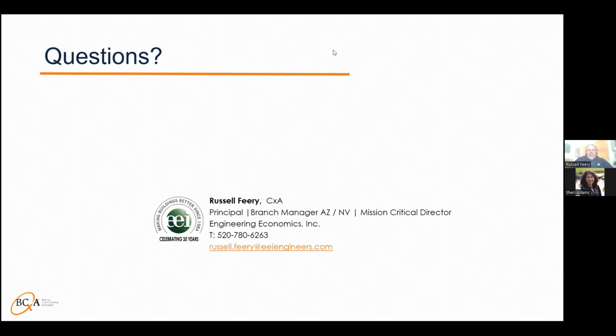Sherry, are you monitoring the Q&A? Yes, it looks like we have, it's not really a question, more of an observation. It says, we've seen that the 6-way valve install on recent projects here in Spokane, they utilize a moisture sensor on the chilled water return. The manufacturer recommends the moisture sensor is installed in the conditioned space, which poses an issue with duct return systems, or when the 6-way valve is located outside the conditioned space, i.e. the corridor instead of in the room.